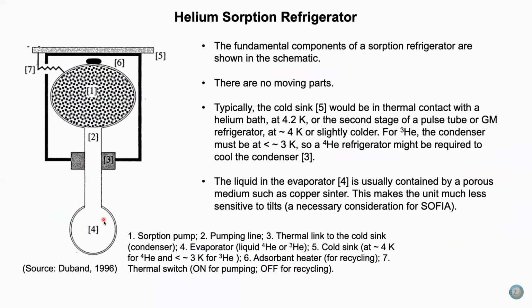There's a very simple schematic of a sorption refrigerator, and it has just a few components. The most important component is the evaporator. This is where you condense liquid, either helium-3 or helium-4. In this case, it would be helium-4. And up here is the sorption pump. It's filled with charcoal, which is a very good cryogenic adsorbent for helium. There's a pumping line in between. This is staged off of some temperature, usually 4 Kelvin. And then there's a heat switch, which connects the cold plate with the sorption pump. And there's a heater also.